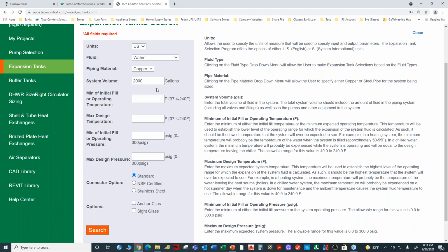System volume, what's the minimum or initial fill or operating temperature? We said that was groundwater temperature, and for New England we said that was 50 degrees. We'll put in 50. The maximum temperature is based on our system design, and we said our boiler was going to put out 180 degrees. The minimum or fill operating pressure we calculated at 40 pounds for our 75-foot tall building. And the maximum pressure we wanted at the suction side of the pump, we said was 110 pounds. We want a standard tank for this first selection.